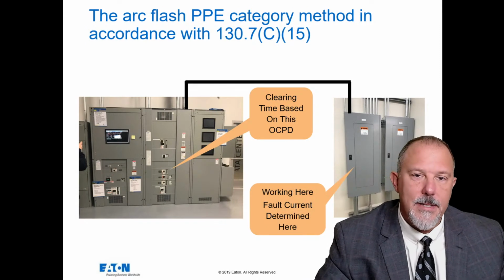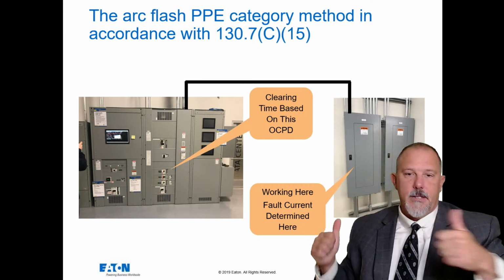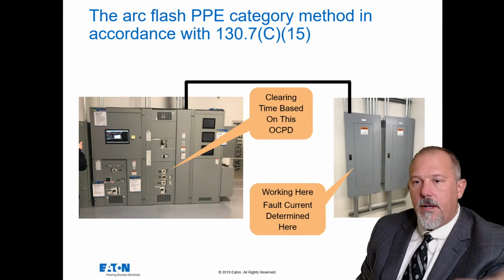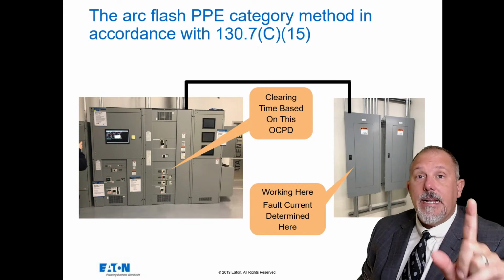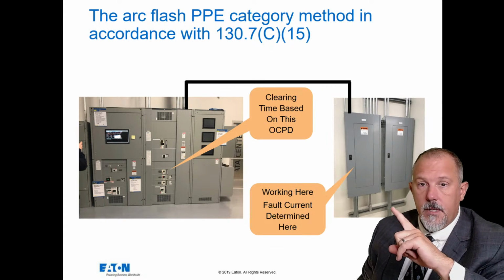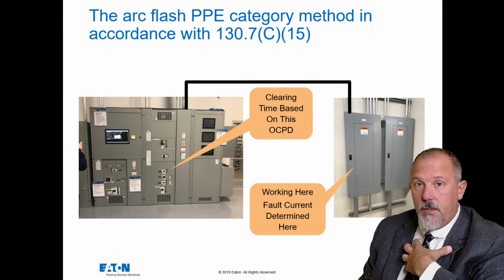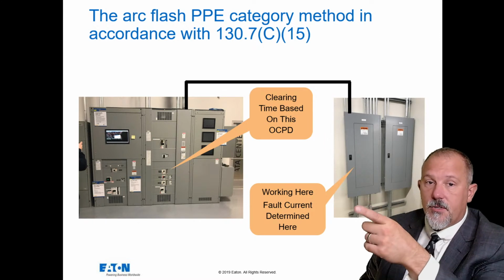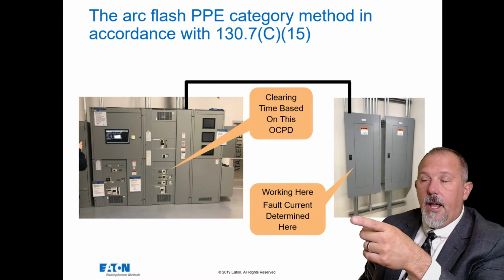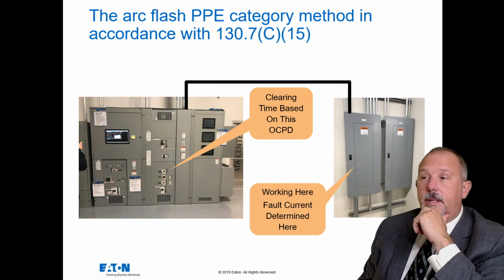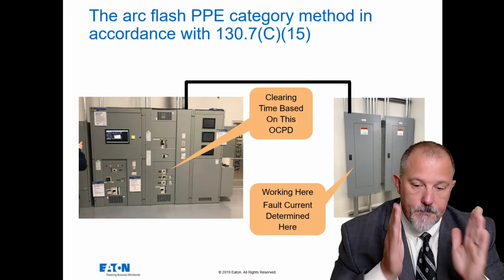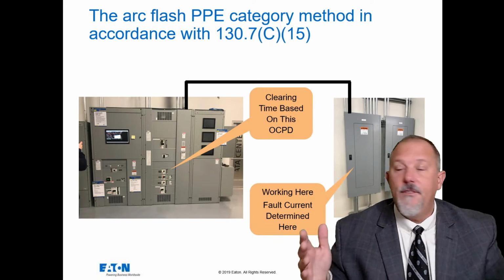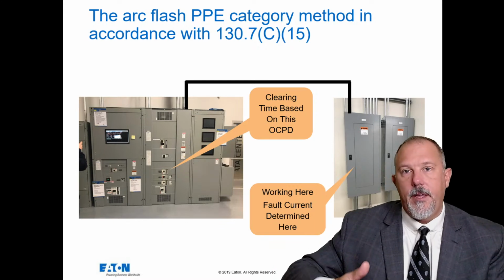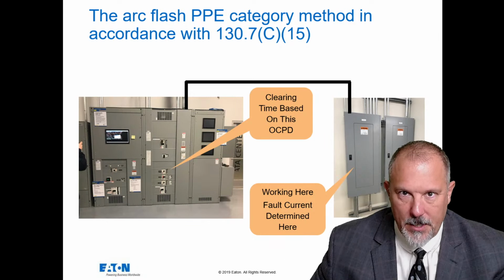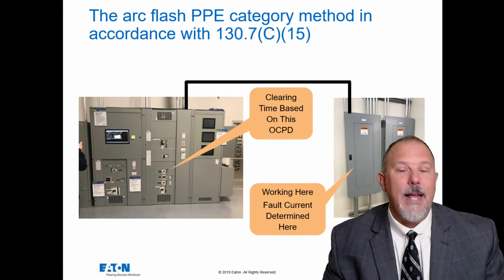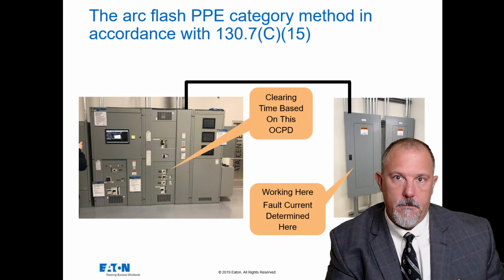All right, so let's take a look at this behind us. So remember when I work on equipment, and let's say I'm going to do justified energized work in this panel, the incident energy that I'm exposed to is dependent upon the clearing time of the upstream overcurrent device over there. And that could be a molded case circuit breaker. It can be a power circuit breaker. And remember that, and I've got programs on this. I can say, for example, an 800 amp breaker. I can buy an 800 amp molded case circuit breaker, an 800 amp insulated case circuit breaker, and an 800 amp power circuit breaker.